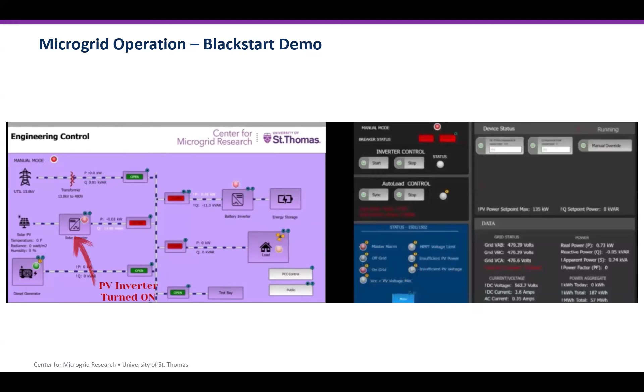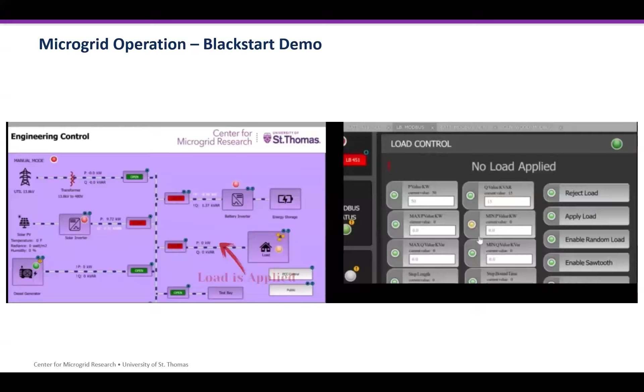Now we are applying the load, a 50 kilowatt load, with some reactive power since the load bank we have is an RL, not just an R. So the load is applied, and you'll find the power is 41 coming from the grid and around 9 kilowatt from the solar, totaling 50, feeding the load itself.